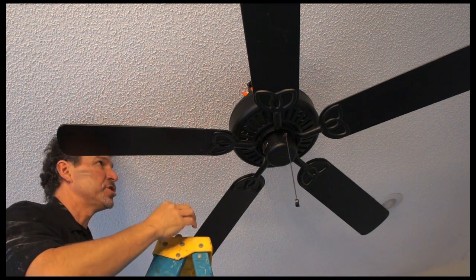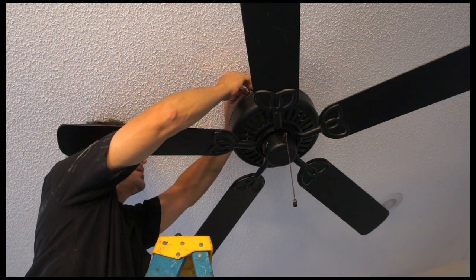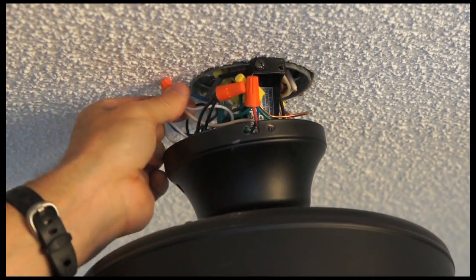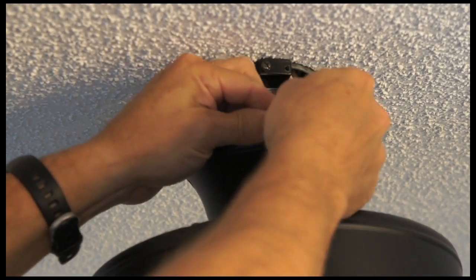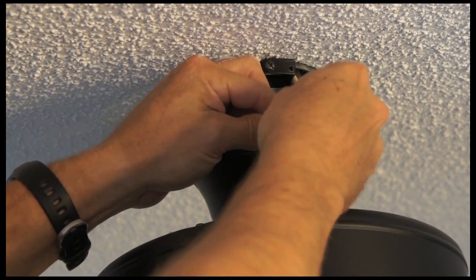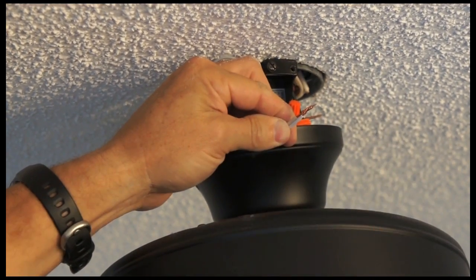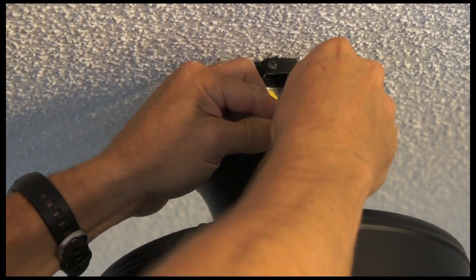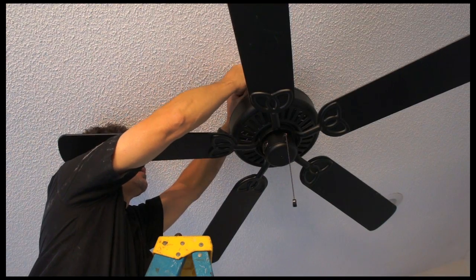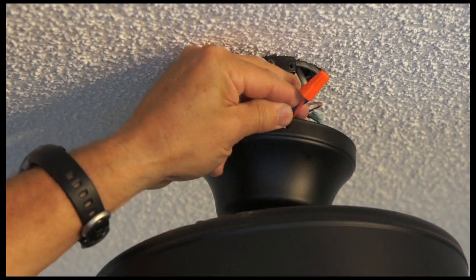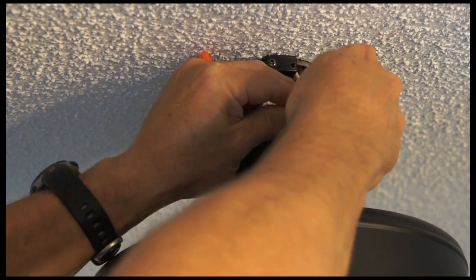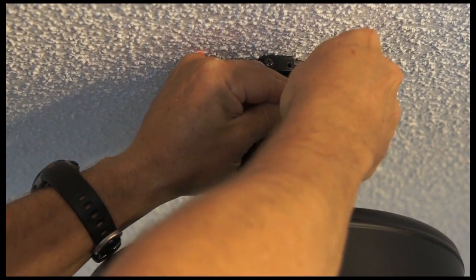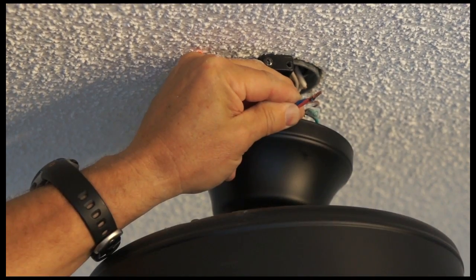So now I'm going to check each connection, white to white. I'm going to remove the wire nuts to make sure the wire hasn't broken off inside. And I'm going to remove my blue to red, which is the controller. And that seems to be good.